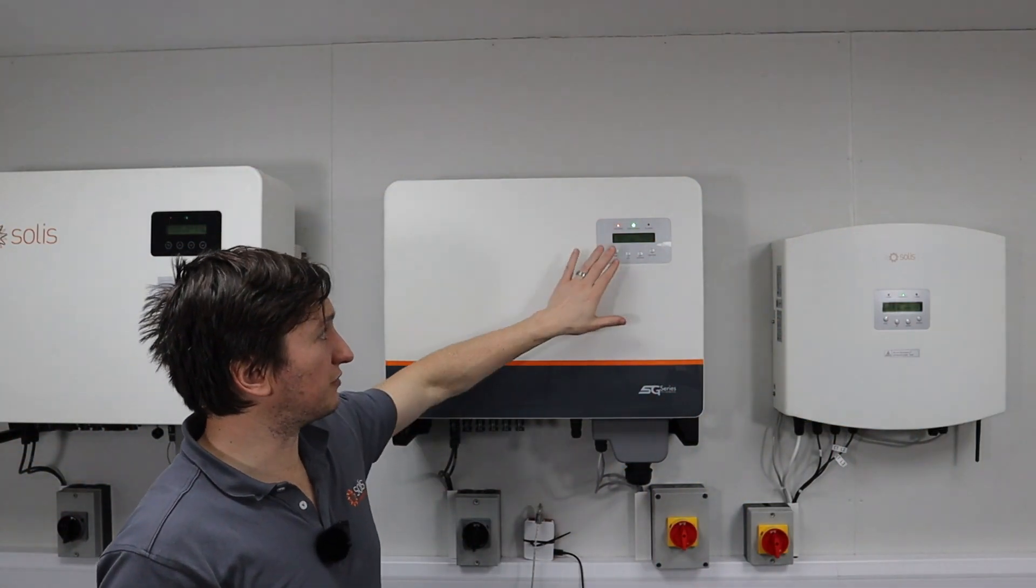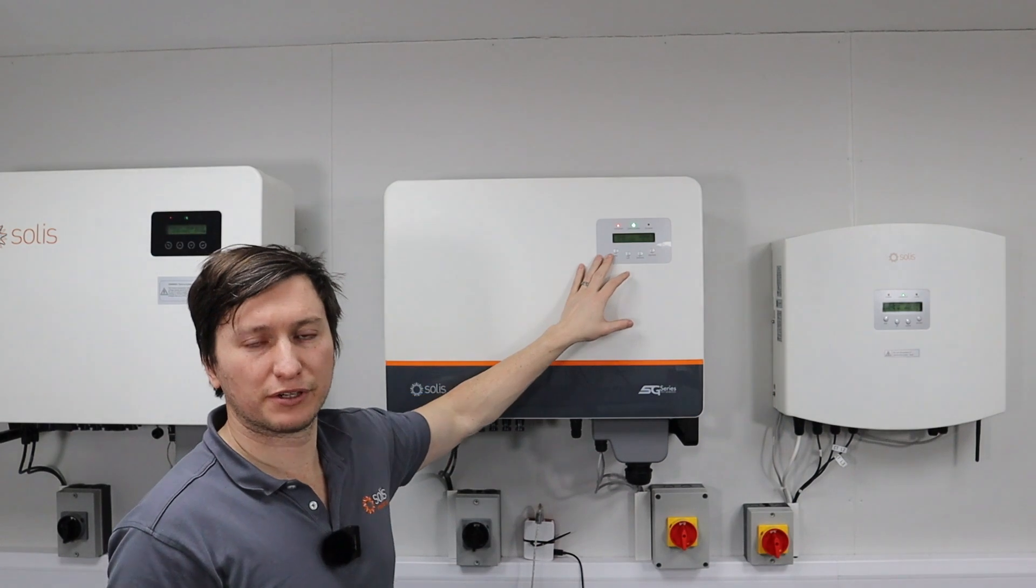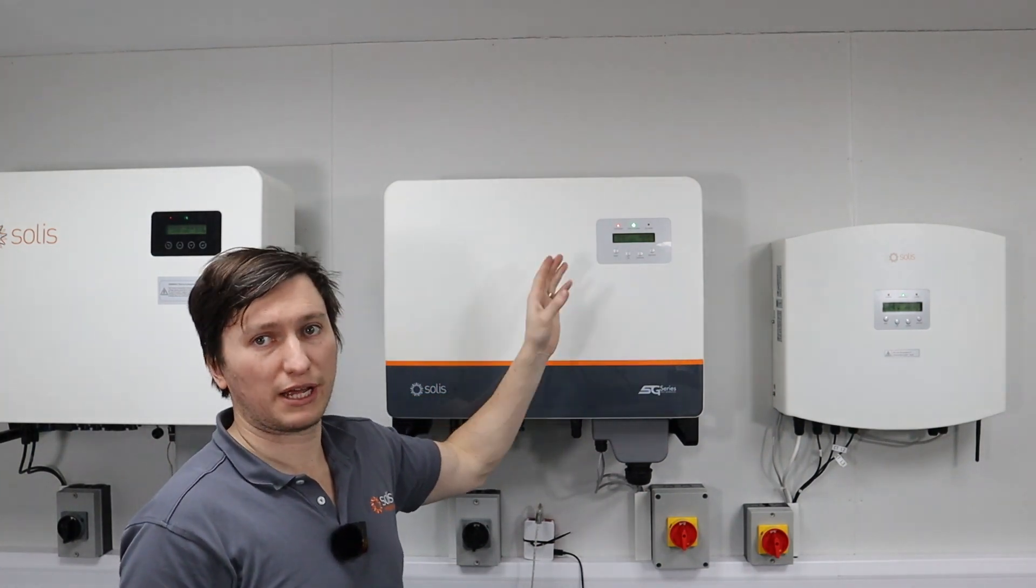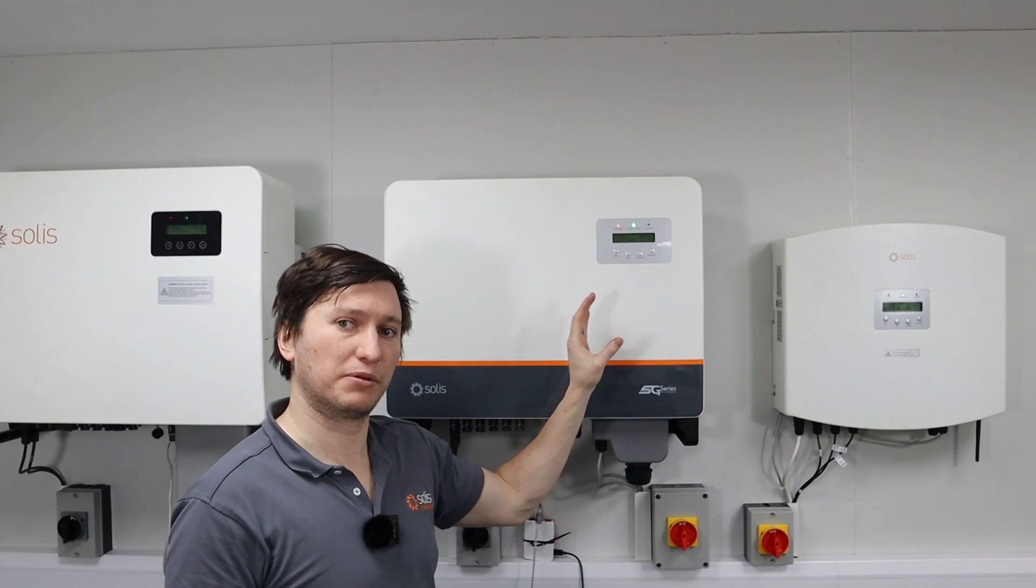Okay, so I've set my other inverter to address two, because I set that one to one. And I did that in settings. I've also enabled failsafe on this inverter. So we've completed the installation now, the EPM is correctly measuring the grid power, and knowing when the export is exceeded. And it's able to control the inverters when that export limit is exceeded. So in a nutshell, we have successfully set it up.